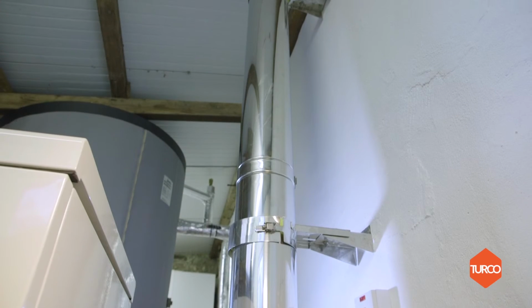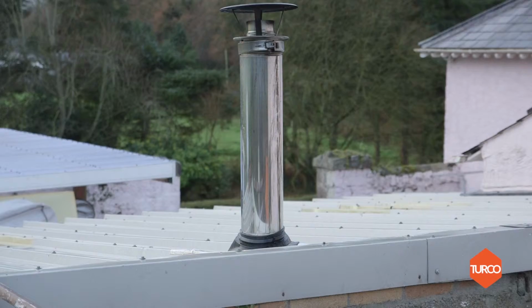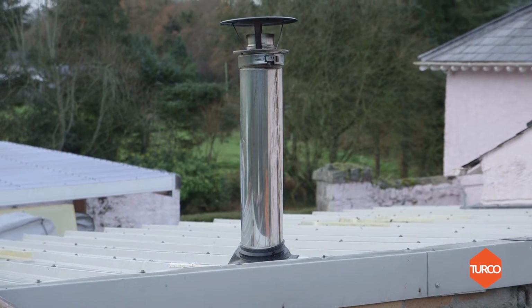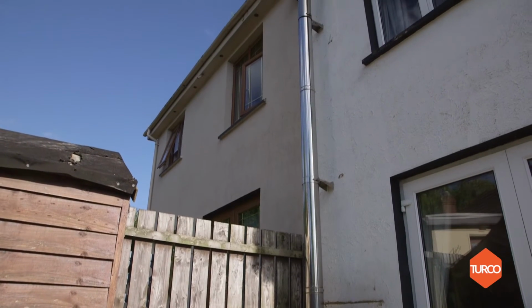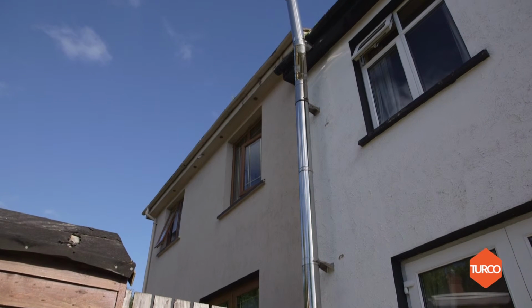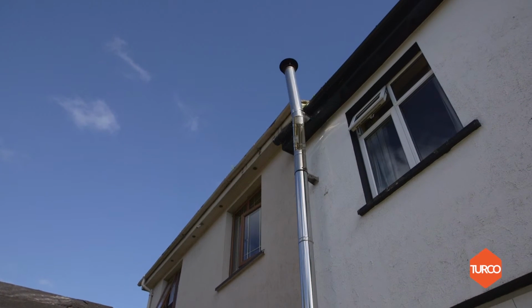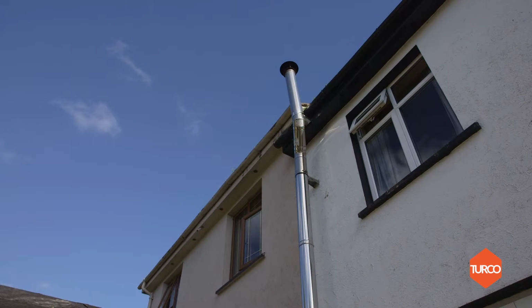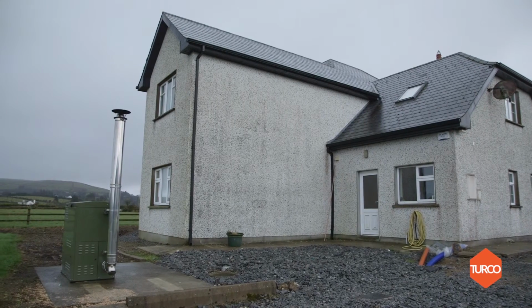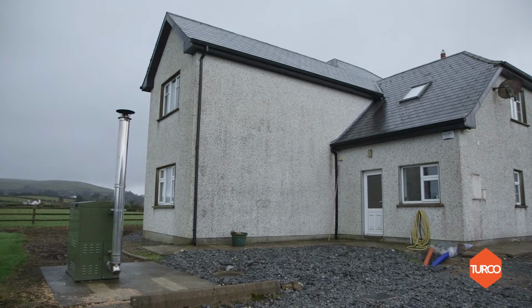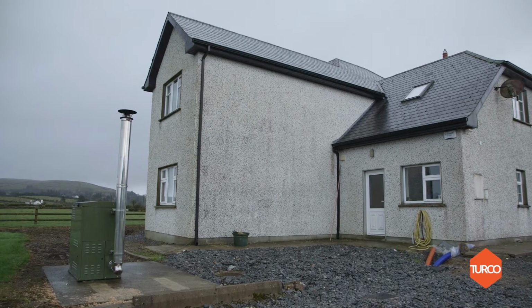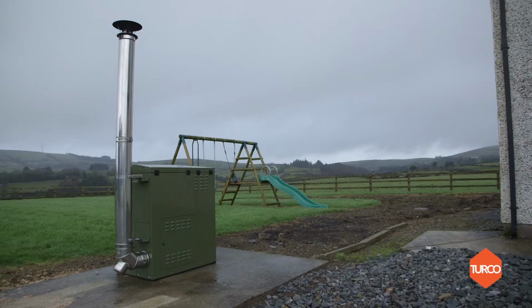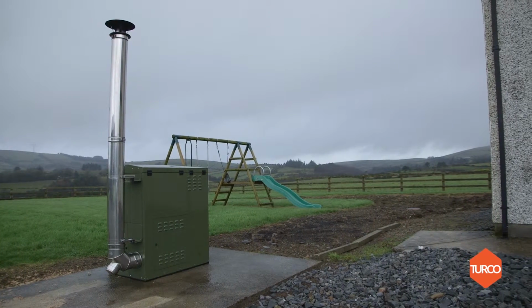In summary, for internal boilers, the flue must terminate at least 1 metre above the eave of the roof. If the boiler is an external boiler, the flue must terminate at least 1 metre above the eave of the roof if located directly beside the building or within 3 metres of the building. Otherwise, if the external boiler is located further than 3 metres from the nearest building or tall structure, the standard shorter flue can be used provided the boiler can run satisfactorily and achieve a draft of 20 pascals.